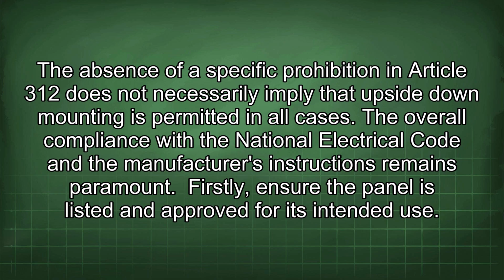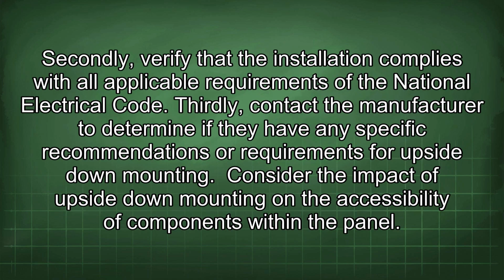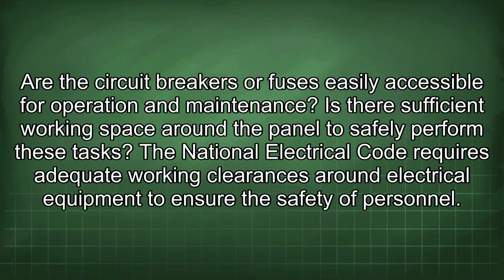Firstly, ensure the panel is listed and approved for its intended use. Secondly, verify that the installation complies with all applicable requirements of the National Electrical Code. Thirdly, contact the manufacturer to determine if they have any specific recommendations or requirements for upside-down mounting. Consider the impact of upside-down mounting on the accessibility of components within the panel. Are the circuit breakers or fuses easily accessible for operation and maintenance? Is there sufficient working space around the panel to safely perform these tasks? The National Electrical Code requires adequate working clearances around electrical equipment to ensure the safety of personnel.